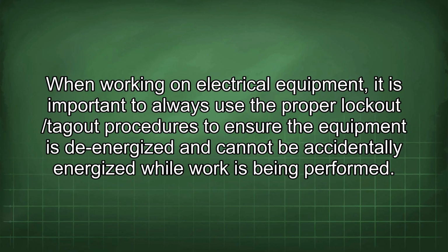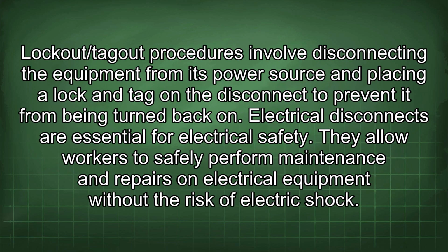When working on electrical equipment, it is important to always use the proper lockout/tagout procedures to ensure the equipment is de-energized and cannot be accidentally energized while work is being performed. Lockout/tagout procedures involve disconnecting the equipment from its power source and placing a lock and tag on the disconnect to prevent it from being turned back on. Electrical disconnects are essential for electrical safety. They allow workers to safely perform maintenance and repairs on electrical equipment without the risk of electric shock.